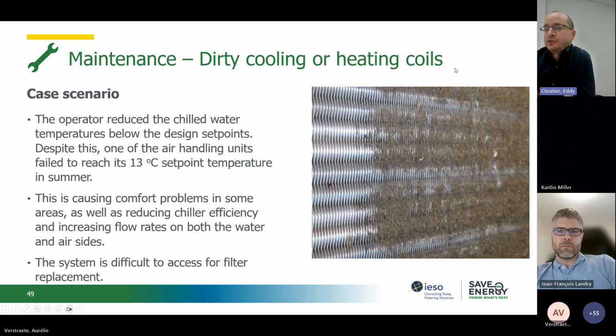So, of course, this was causing comfort problems in some areas, as well as reducing chiller efficiency and increasing flow rate on both the water and air side. The problem was caused because the system was really difficult to access for maintenance and operation, and the filter replacement was not done on a sufficient basis.